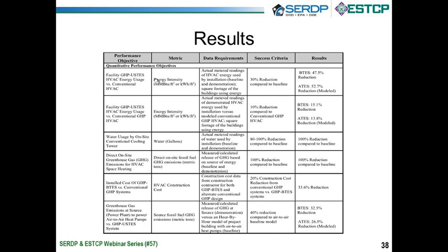But as you can imagine, if you put, in the example of us, more heat in the ground than you take out long term, guess what? The ground's going to warm up. The water's going to warm up. All this hard work you did of getting the high efficiency on the front end is going to fade. With BTES or ATES and these auxiliary heat rejection devices, our goal is for the efficiency to get better each year, to actually take more heat out of the ground than we're dumping in there so we can get lower, as an example, condenser water.